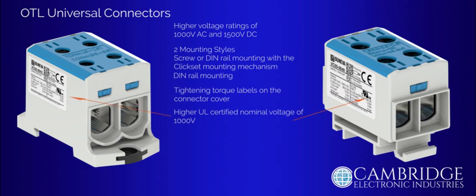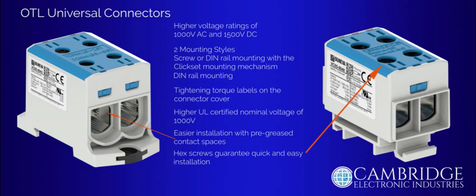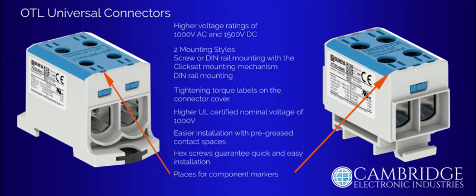All Ouneva products are CE and UL certified. These are clearly marked on the label, and the OTL blocks have been certified for higher nominal voltages of 1000 volts. The connectors have pre-greased contact spaces. This, coupled with the hex screws to the top of the connector block, ensure quick and easy installation. Each block has places for component markers for easy cable identification. The spaces accept 5mm wide markers of the Partex TX range.